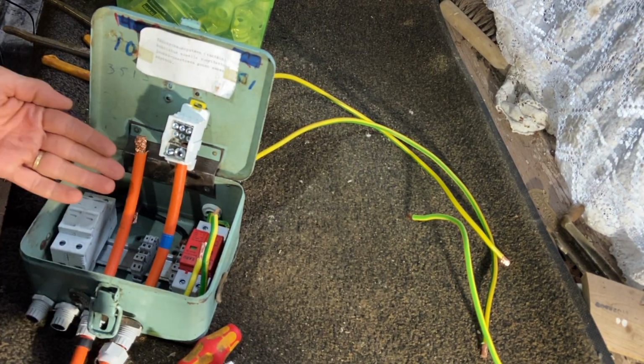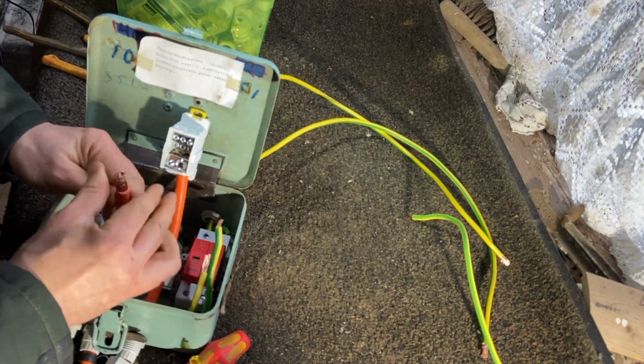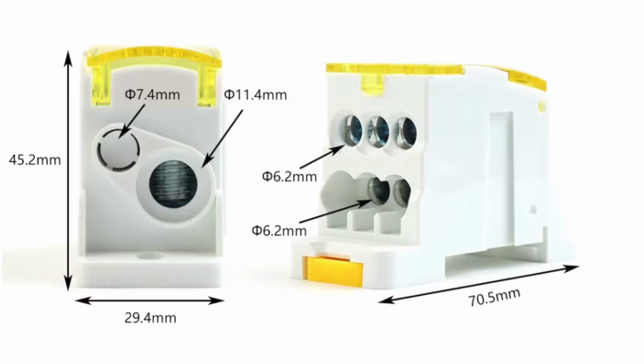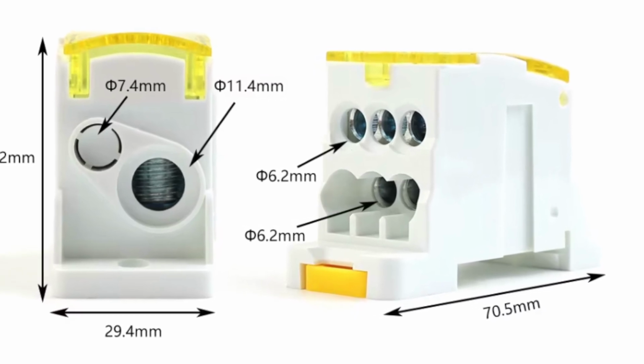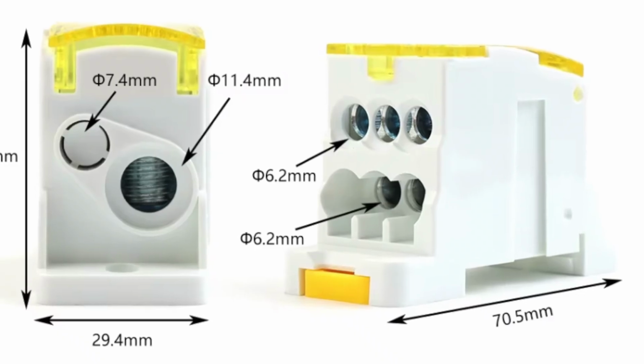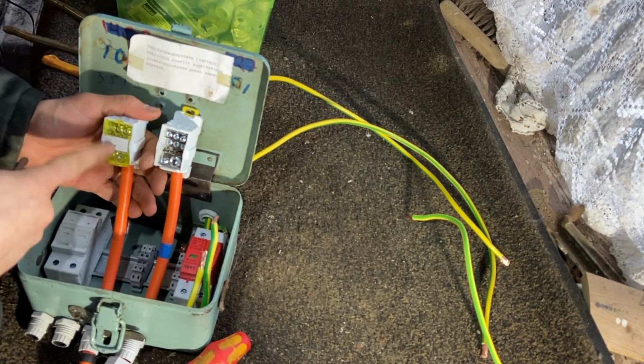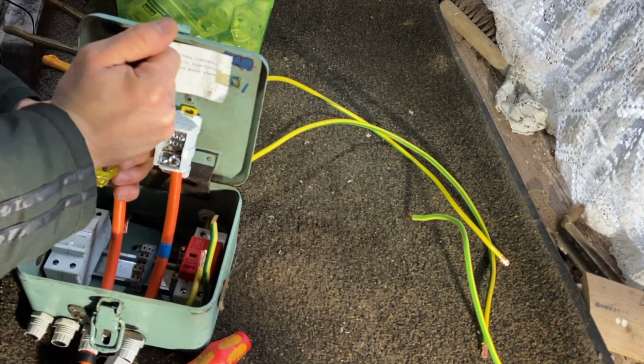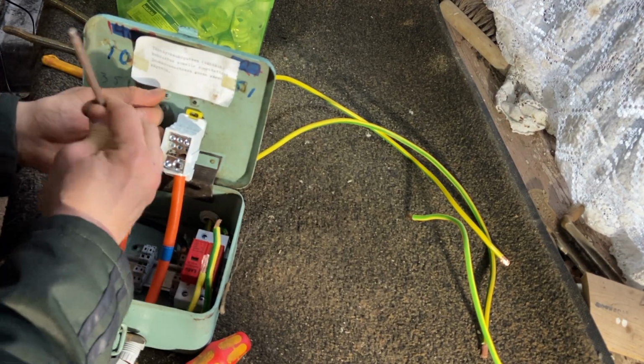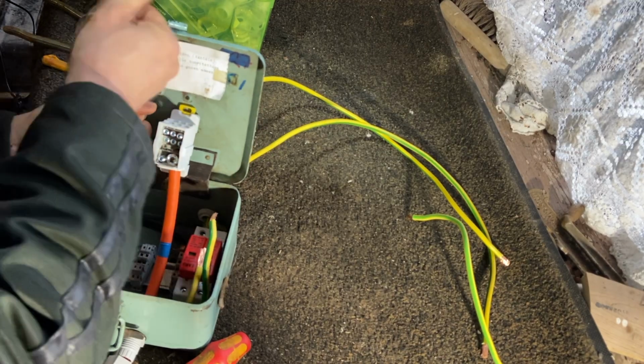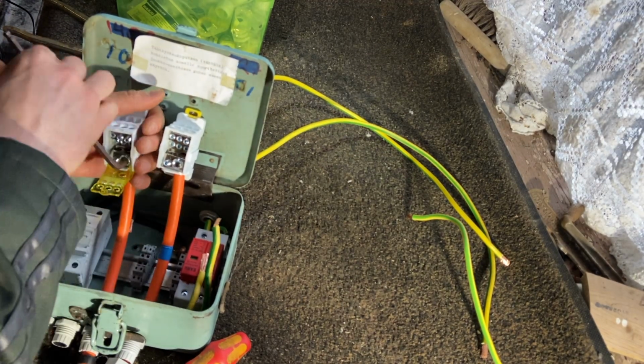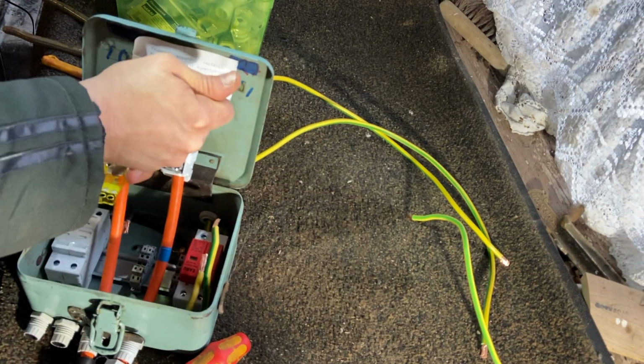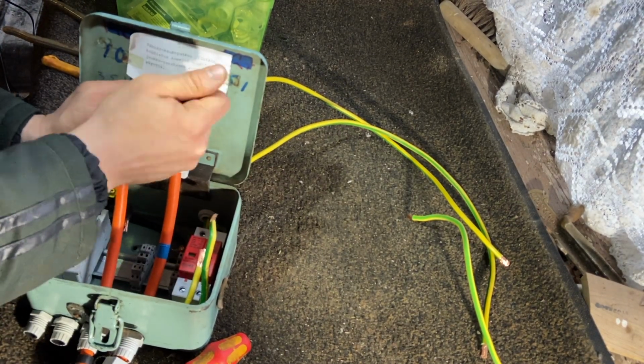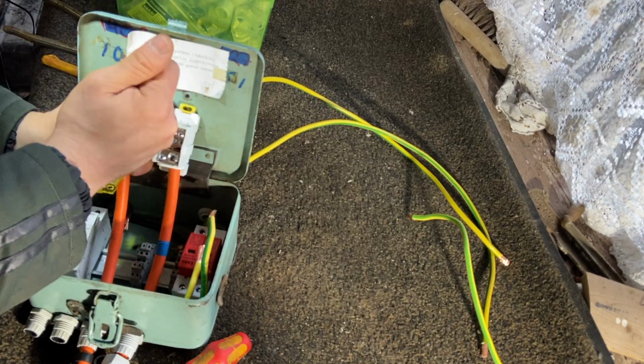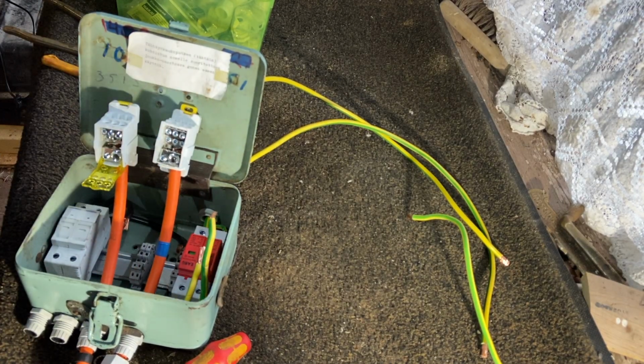On the center there's a terminal block. The big hole is for the high voltage cables, and from there cables go to the surge protection on the right side, as well as the DC fuses on the left side. From the DC fuses a cable goes out to the inverter eventually, though it's not connected in this picture.